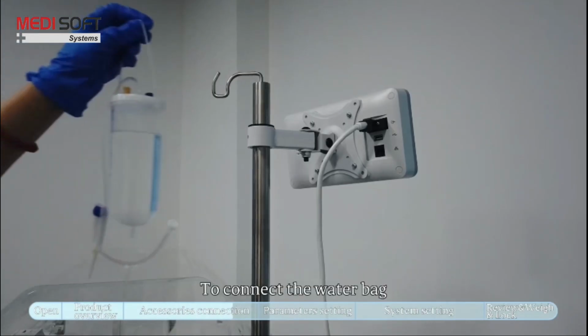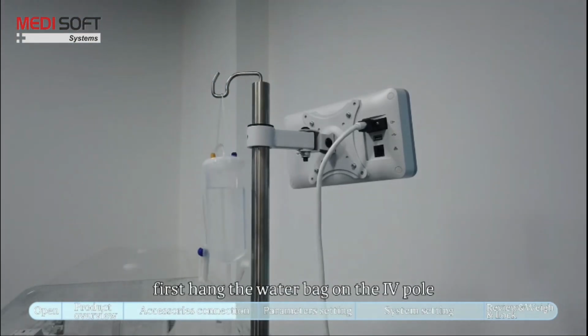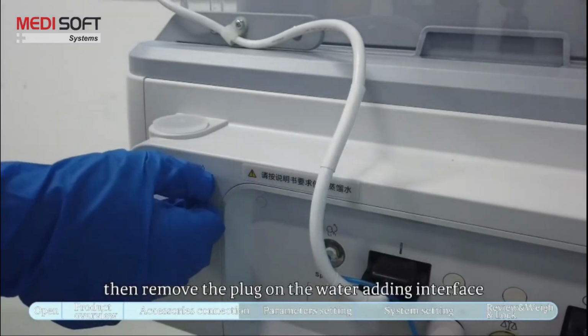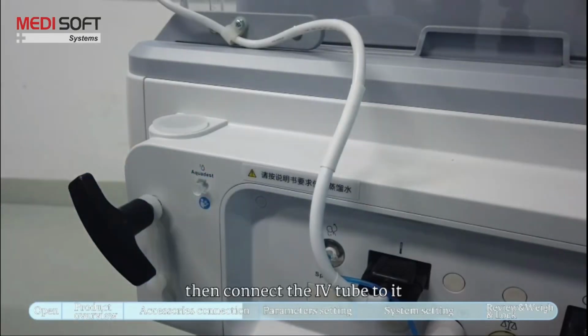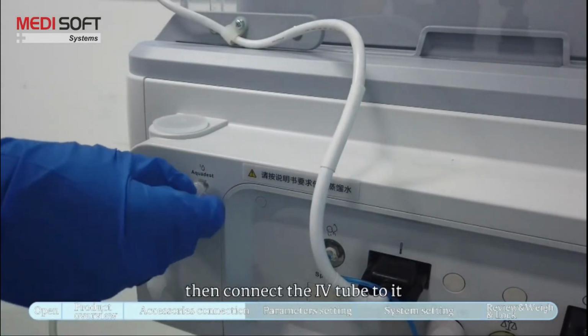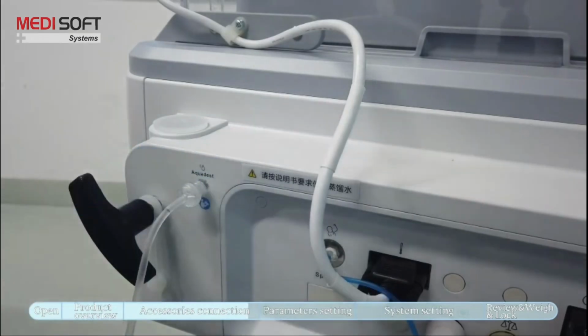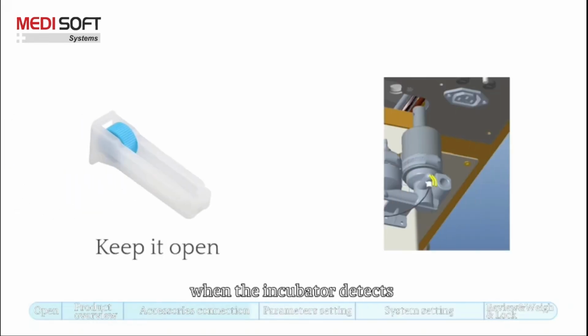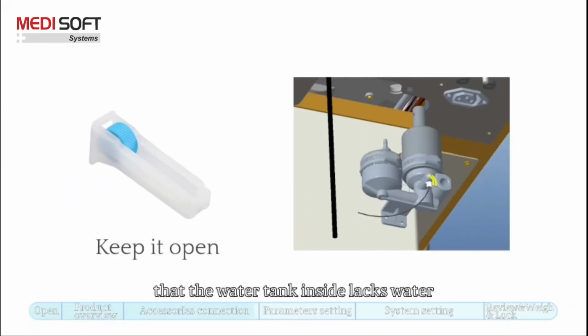To connect the water bag, first, hang the water bag on the IV pole, then remove the plug on the water adding interface. Then connect the IV tube to it. Keep the roller clamp open. When the incubator detects that the water tank inside lacks water, it will automatically add water.